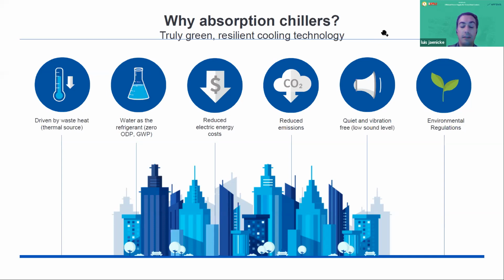Of course, absorption chillers will drastically reduce the power consumed by the chiller plant in a data center, and this power saving comes with savings in CO2 emissions. If I'm not consuming that amount of power, I'm not releasing all the CO2 equivalent to the generation of that power. Also, absorption chillers produce the cooling with a chemical process, so there is no compressor inside. This is replaced by a few small pumps. So it's also a very quiet and vibration-free piece of equipment compared with mechanical or more traditional chillers.